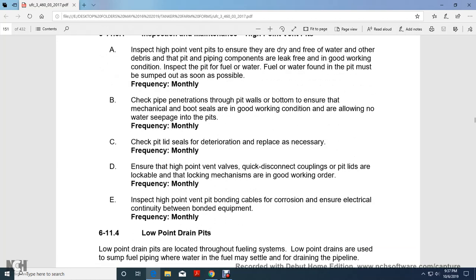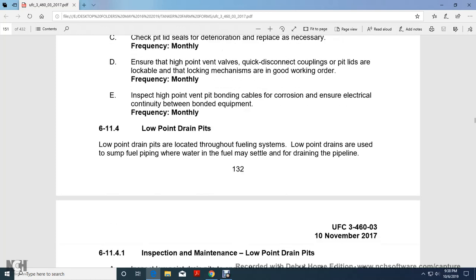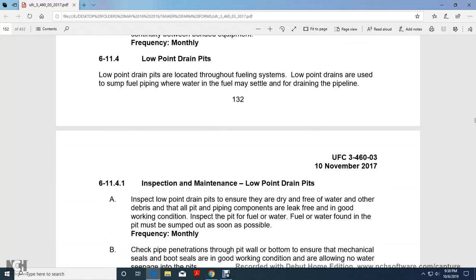Monthly, check the pit seals for deterioration and replace as necessary. Ensure the high point vent valve, quick disconnect couplings, and pit lids are lockable and the locking mechanisms are in good working order, monthly. Inspect the high point pit bonding cable for corrosion and ensure electrical continuity between bonded equipment, monthly.